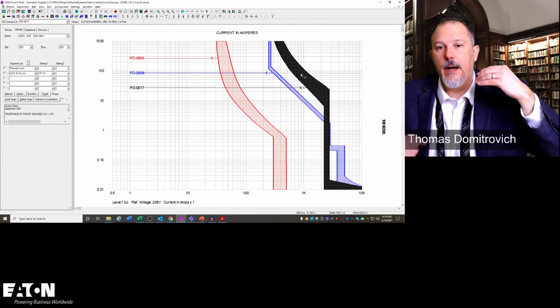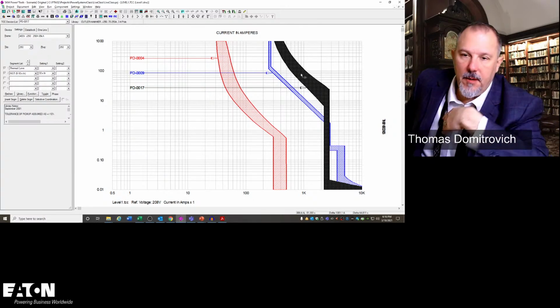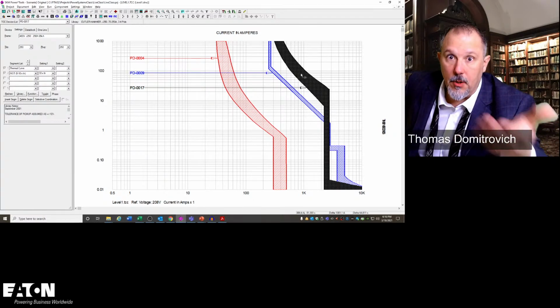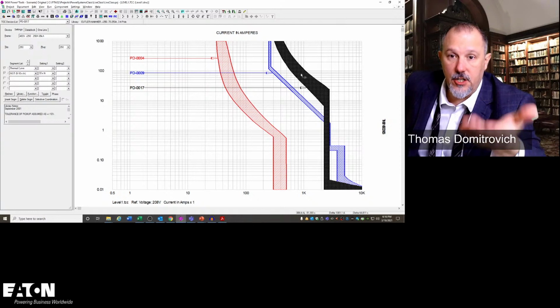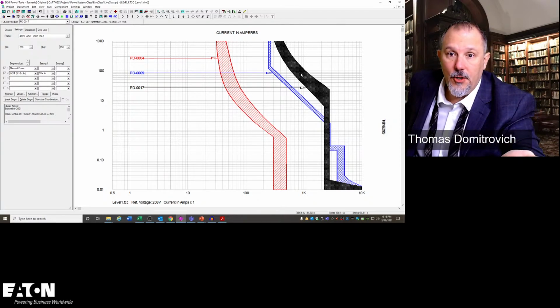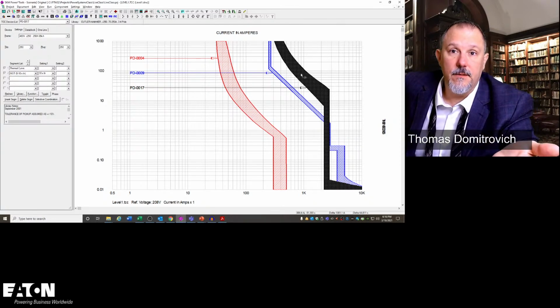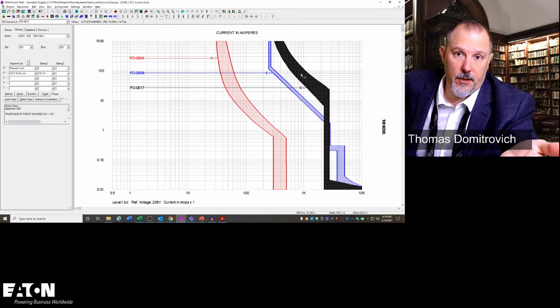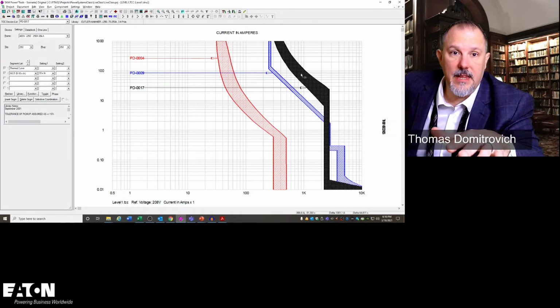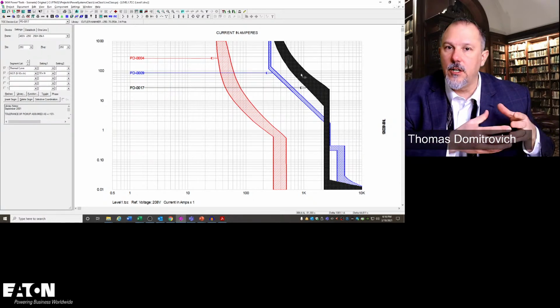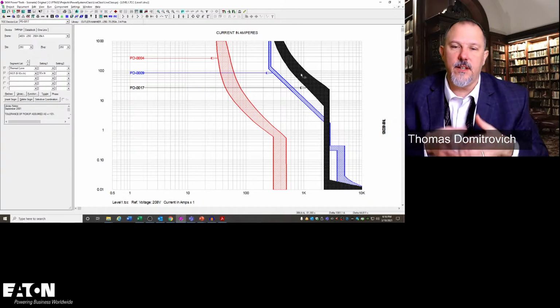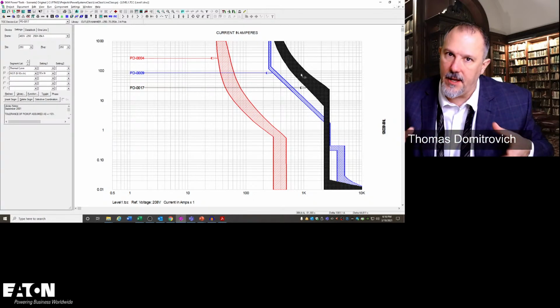So he walked down the system. He got me the trip curves, and I plotted them for him. And I demonstrated. I showed him. I said, look, you don't coordinate. You don't even coordinate on the ground fault currents. Nobody looked at that. Now, it's not a life safety. It wasn't an Article 700. It was a 702 system. It was an optional standby system.